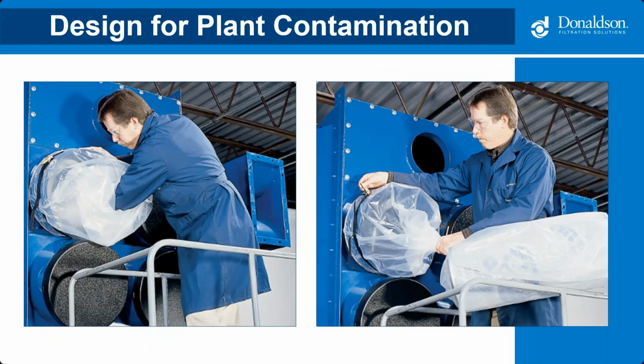Because battery dust can be toxic and carcinogenic, an appropriate level of plant and personal protection is required when handling the filters and collected dust from the process. Pretty much all of the manufacturing facilities that I work with utilize a bag in, bag out process for handling dirty filters. I highly recommend putting this in your spec. Bag in, bag out allows the operator to load and unload the filters into the dust collector while minimizing dust exposure to the personnel and the facility. And we also have options for bagging out the collected material below the hopper.